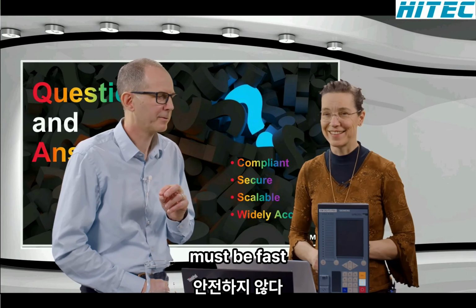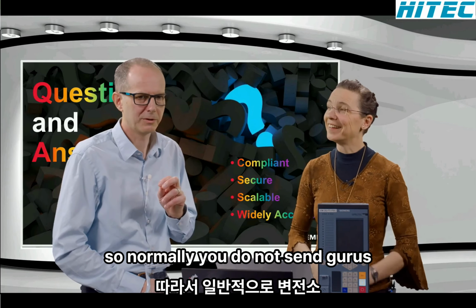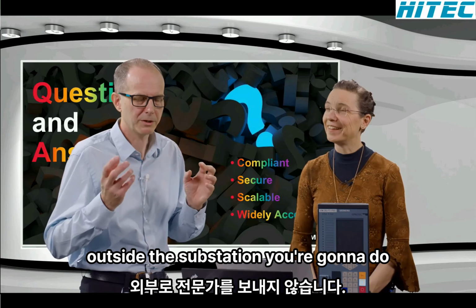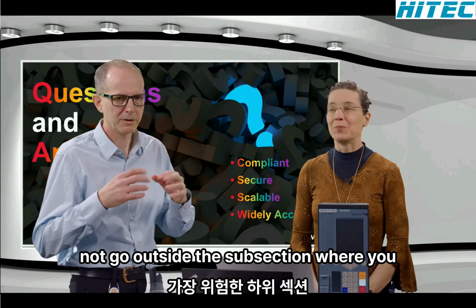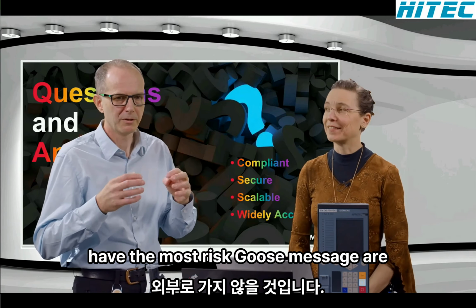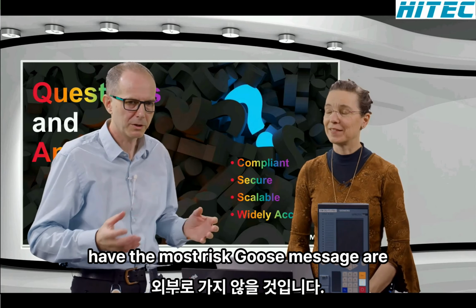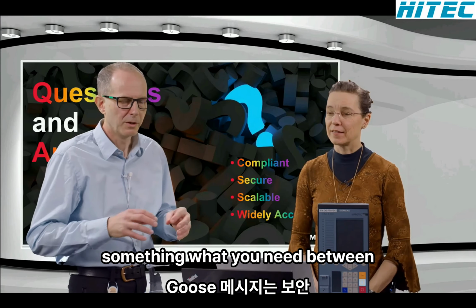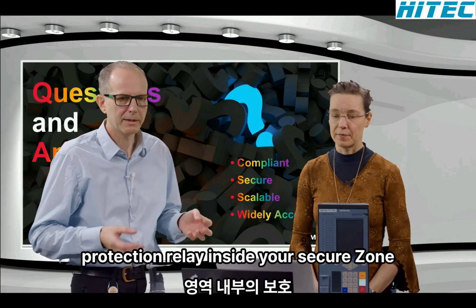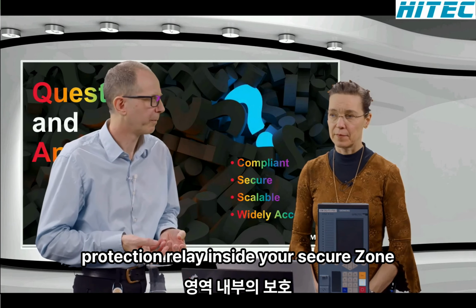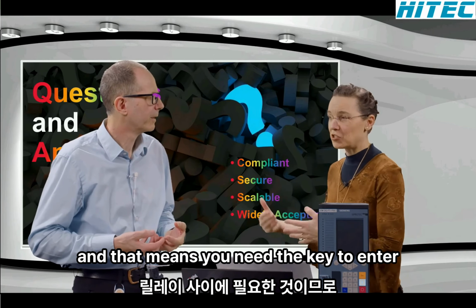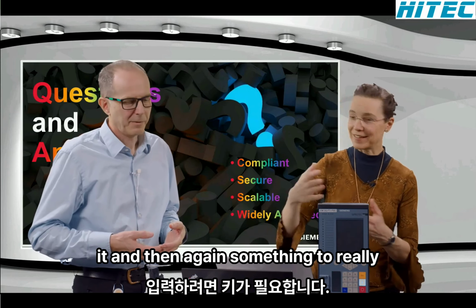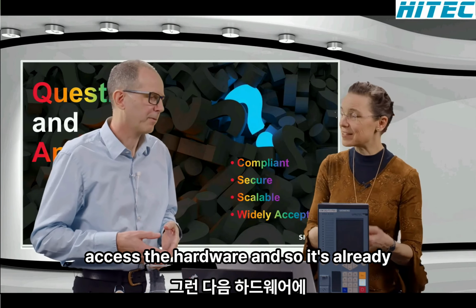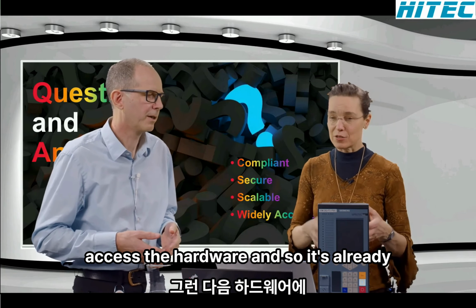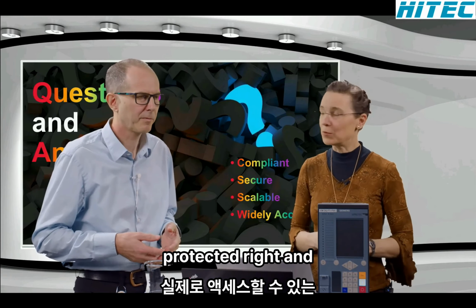So normally you do not send GOOSE outside the substation. You do not go outside where you have the most risk. GOOSE messages are what you need between protection relays inside your secure zone. That means you need a key to enter, and then something again to really access the hardware, so it's already protected, right?